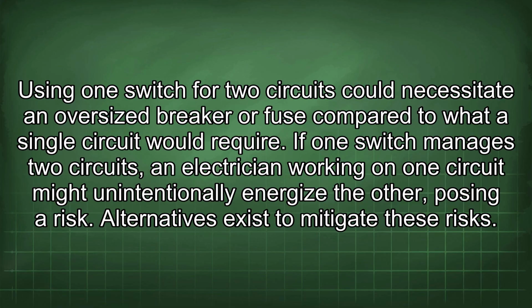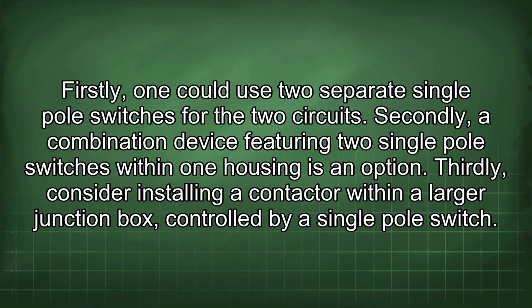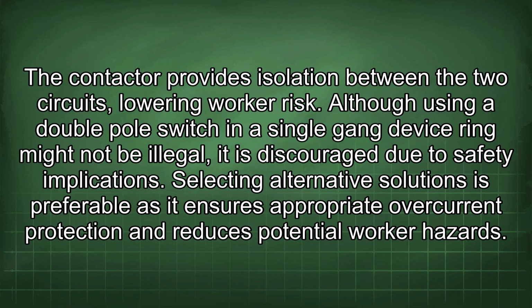risk. Alternatives exist to mitigate these risks. Firstly, one could use two separate single-pole switches for the two circuits. Secondly, a combination device featuring two single-pole switches within one housing is an option. Thirdly, consider installing a contactor within a larger junction box controlled by a single-pole switch. The contactor provides isolation between the two circuits, lowering worker risk. Although using a double-pole switch in a single-gang device ring might not be illegal, it is discouraged due to safety implications. Selecting alternative solutions is preferable as it ensures appropriate overcurrent protection and reduces potential worker hazards.